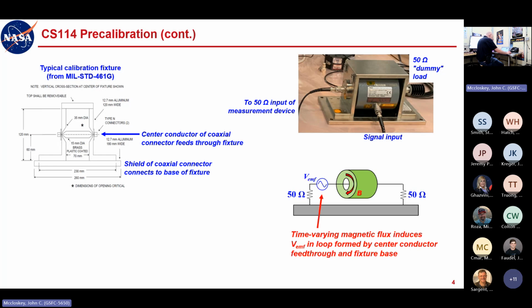But one way or another, you have a pair of 50 ohm loads, one on either side of the cal fixture, and your time-varying magnetic flux induces an EMF in the loop formed by the center conductor feed-through and the fixture base. You're only reading half of the injected potential. Your calibration potential—you're only tapping off one of these 50 ohm loads, but you're inducing this EMF that is in this loop, right? So the 50 ohm resistances are essentially in series from that standpoint, meaning you're only looking at half of the injected potential.